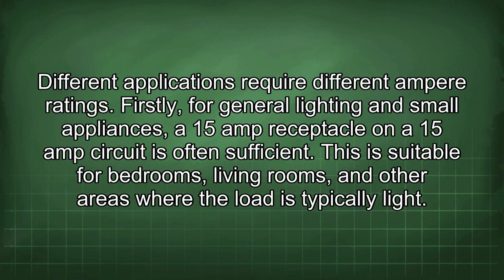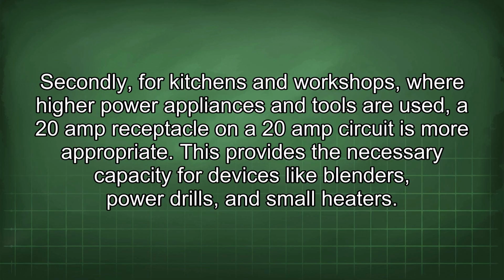Different applications require different ampere ratings. Firstly, for general lighting and small appliances, a 15 amp receptacle on a 15 amp circuit is often sufficient. This is suitable for bedrooms, living rooms, and other areas where the load is typically light. Secondly, for kitchens and workshops, where high power appliances and tools are used, a 20 amp receptacle on a 20 amp circuit is more appropriate. This provides the necessary capacity for devices like blenders, power drills, and small heaters.